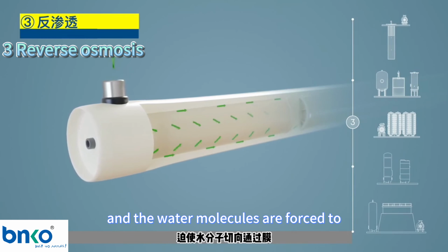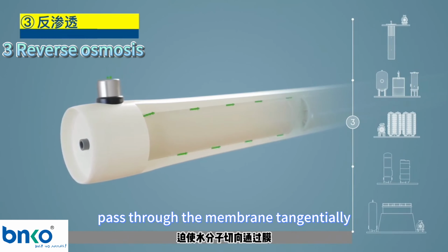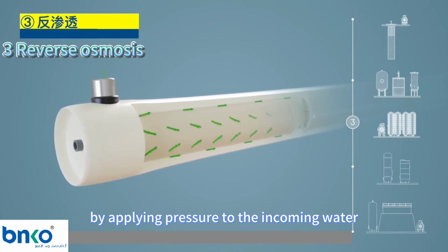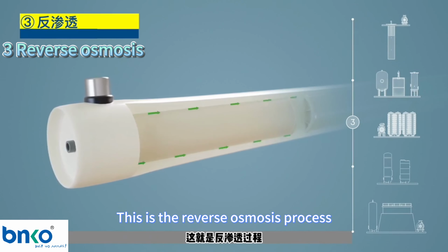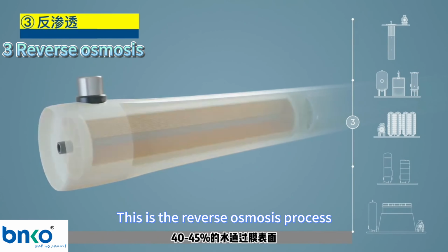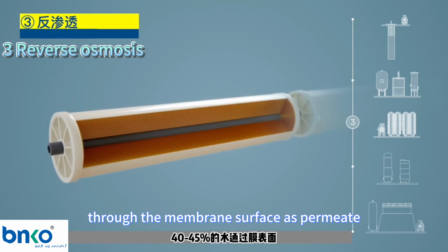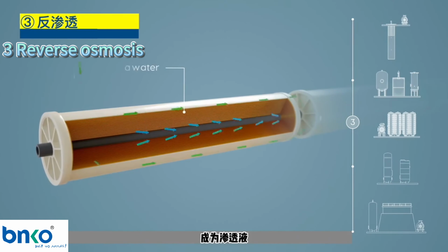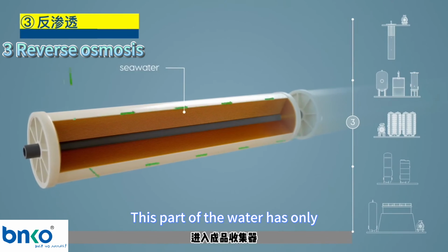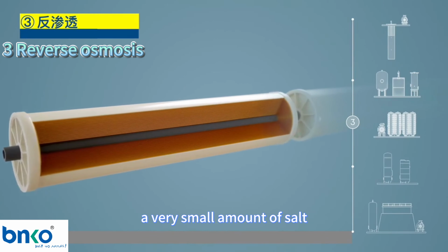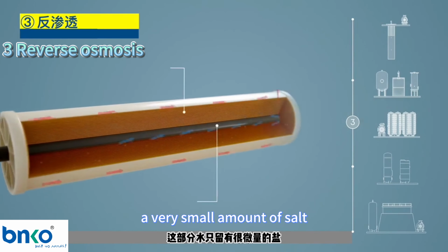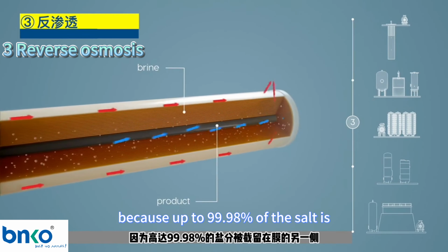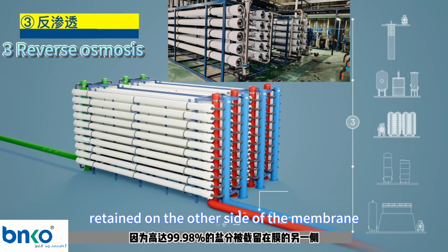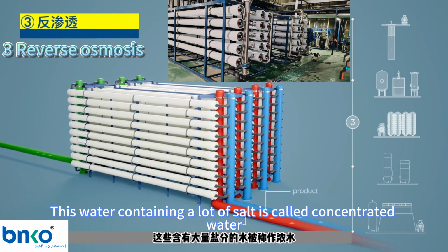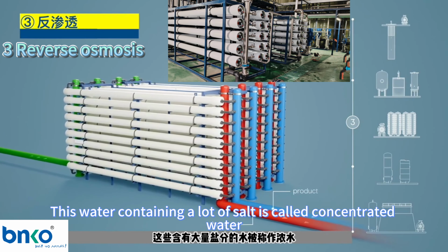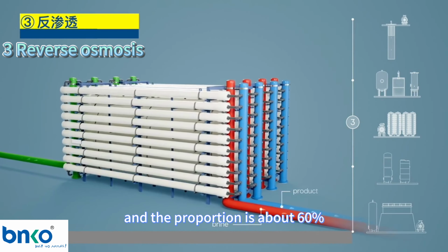and the water molecules are forced to pass through the membrane tangentially by applying pressure to the incoming water. This is the reverse osmosis process. 40% to 45% of the water passes through the membrane surface as permeate and enters the finished product collector. This part of the water has only a very small amount of salt, because up to 99.98% of the salt is retained on the other side of the membrane. This water containing a lot of salt is called concentrated water, and the proportion is about 60%.